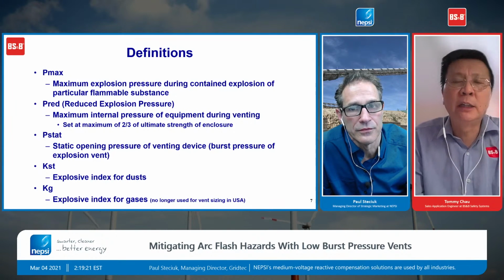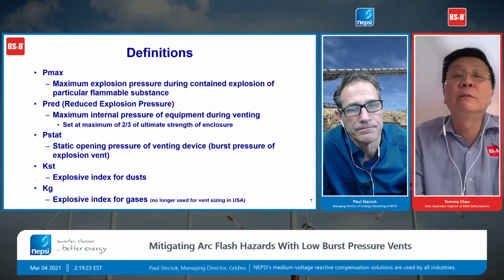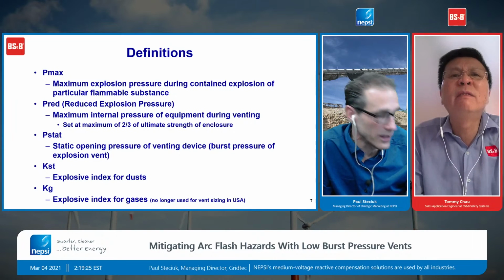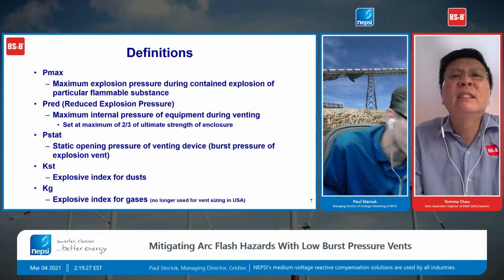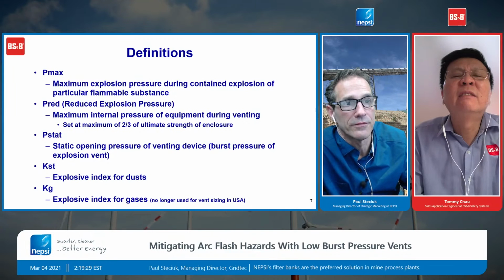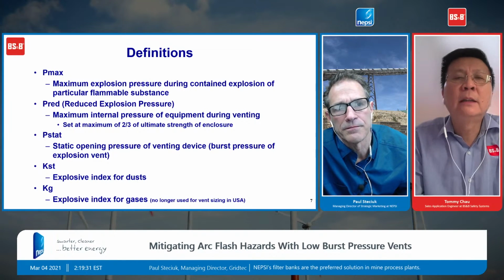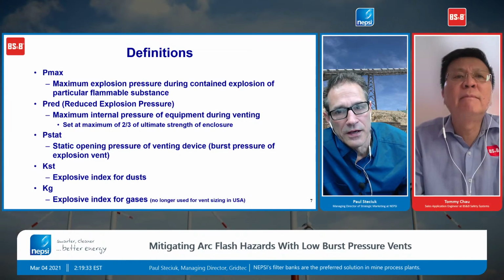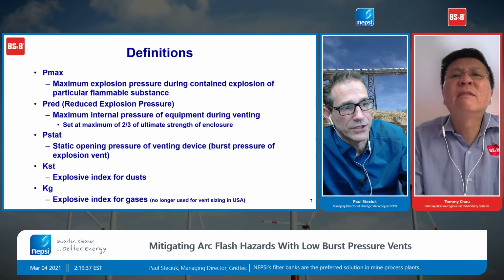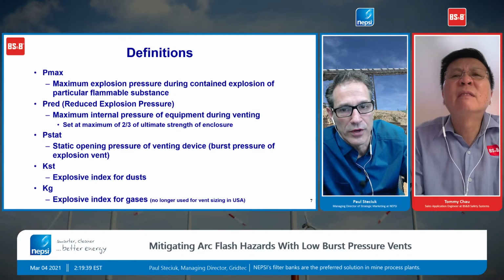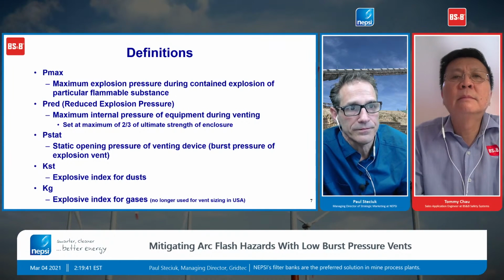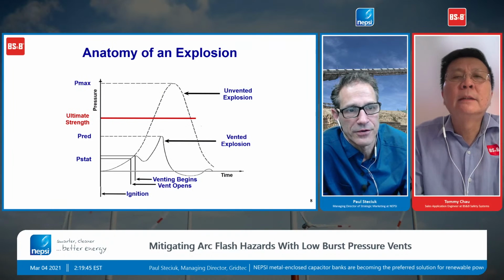And then on the next slide, you have the anatomy of an explosion. P-stat, I think, is actually one of the values on your nameplate. Am I correct on that? Yes, you're correct. And then KST is basically the explosive index, which I want to talk about a little bit, which is the rate of rise of the pressure that you get from a dust explosion. Okay, so here you go.